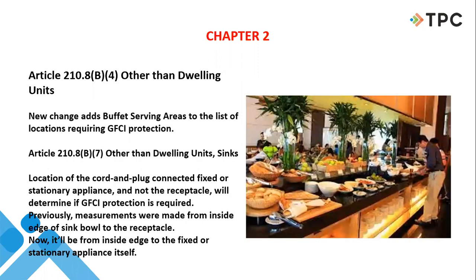In other than dwelling units, these serving areas, buffet areas, things like this, GFCI protection is required. The location of cord and plug connected fixed or stationary appliances, and not the receptacle, will determine if GFCI protection is required. Used to be, measurements were made from, say, the inside edge of the sink bowl to the receptacle. Now it's from the inside edge to the fixed or stationary appliance itself.